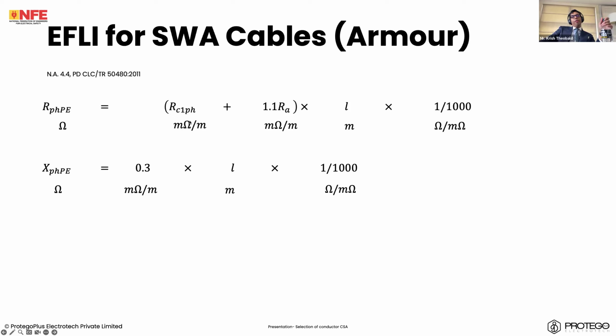For the resistive component, first we take milliohms per meter for the loop of R1, R2, or line and PE, and we add it to the value of the armor. So this is the case where only the armor is used as the protective earth conductor, not the armor and a separate conductor. For the phase conductor, we take the value like we have always done. We add it with 1.1 times the resistance of the armor. And this is our R1, R2. So phase conductor plus 1.1 times the armor. Multiply this by the length, multiply by 1, divide by 1000, effectively to get our resistive component.